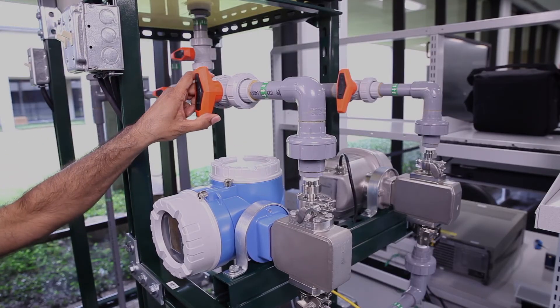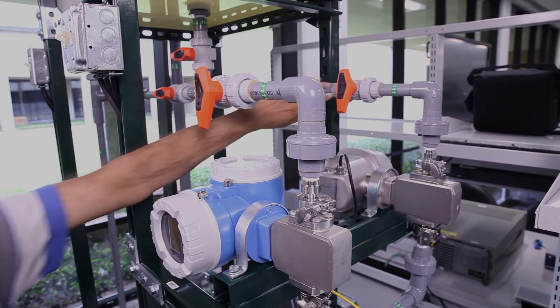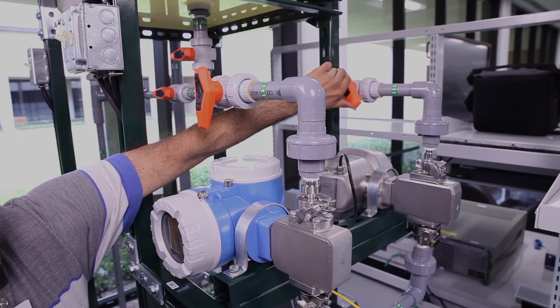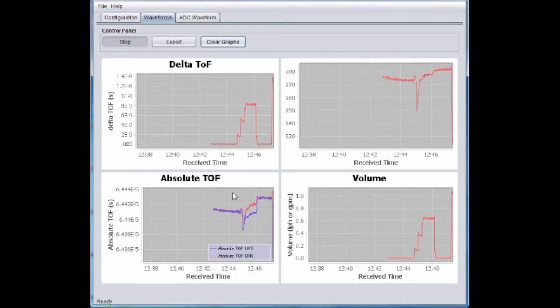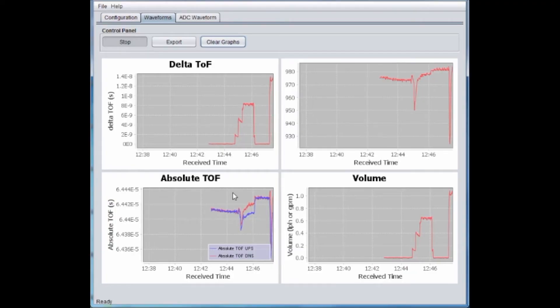Now we will use the right arm of the flow setup for higher flow rates. We can again see the computed TOF respond to the changes in the flow rates.